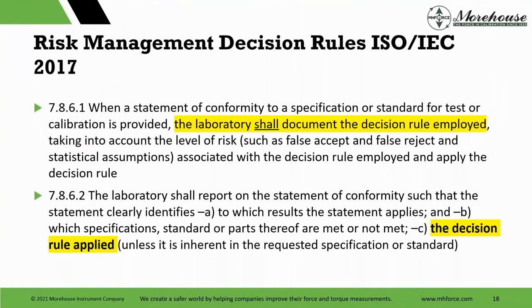It just takes forever in our community to bring these things up, because now we're talking about them. And we're talking about them because the 2017 standard, specifically in 7.8.6.1 and 7.8.6.2, now they're saying, hey, instead of just taking measurement uncertainty into account, now we shall document the decision rule employed, taking into account the level of risk, such as false accept and false reject, and statistical assumptions.